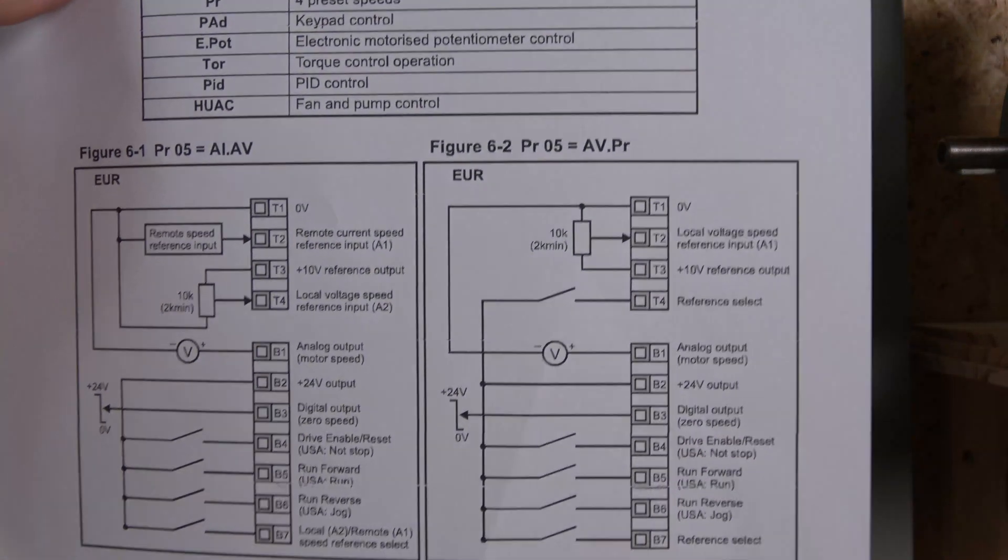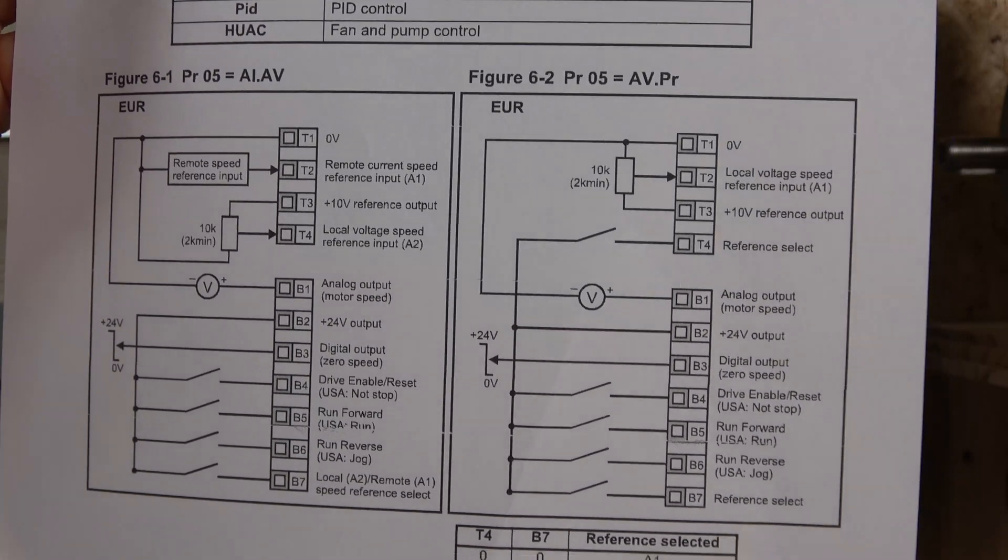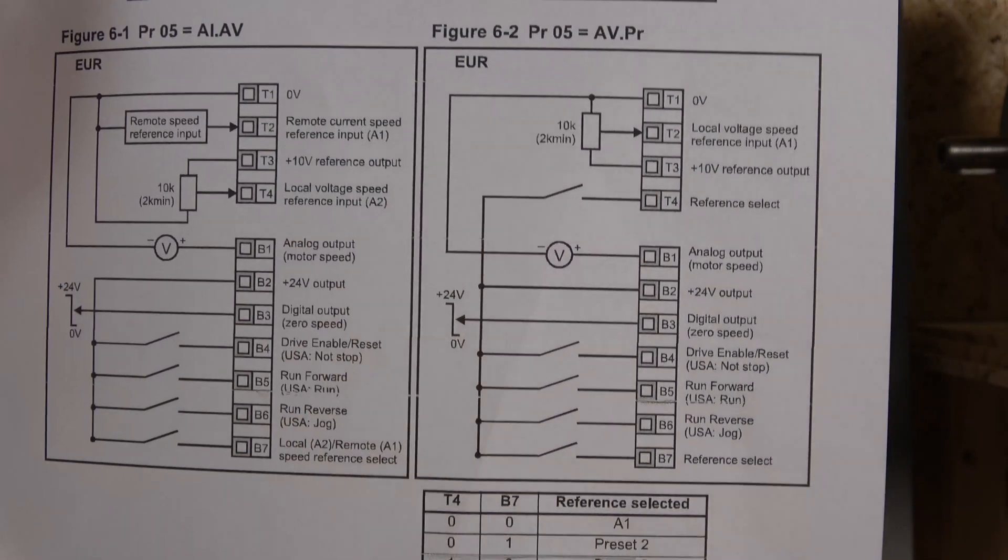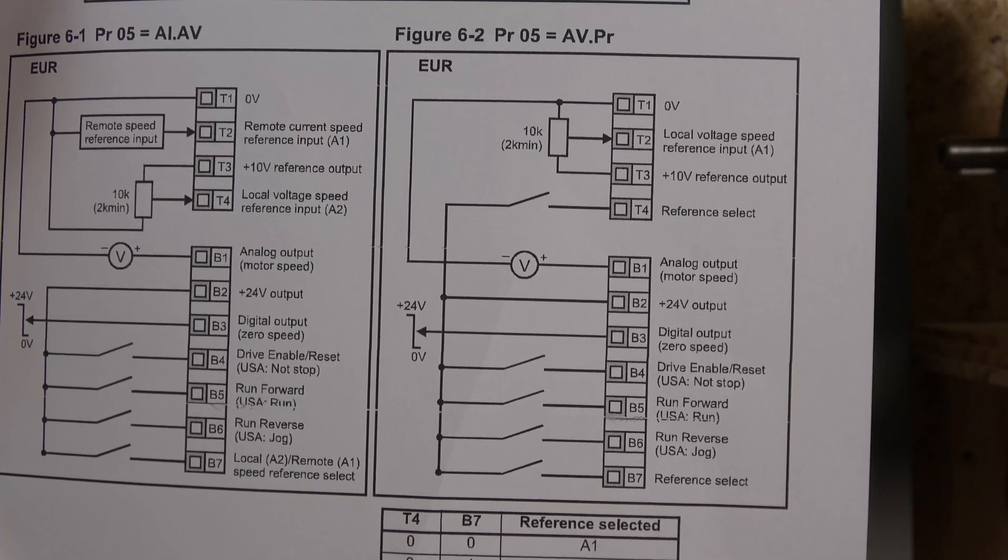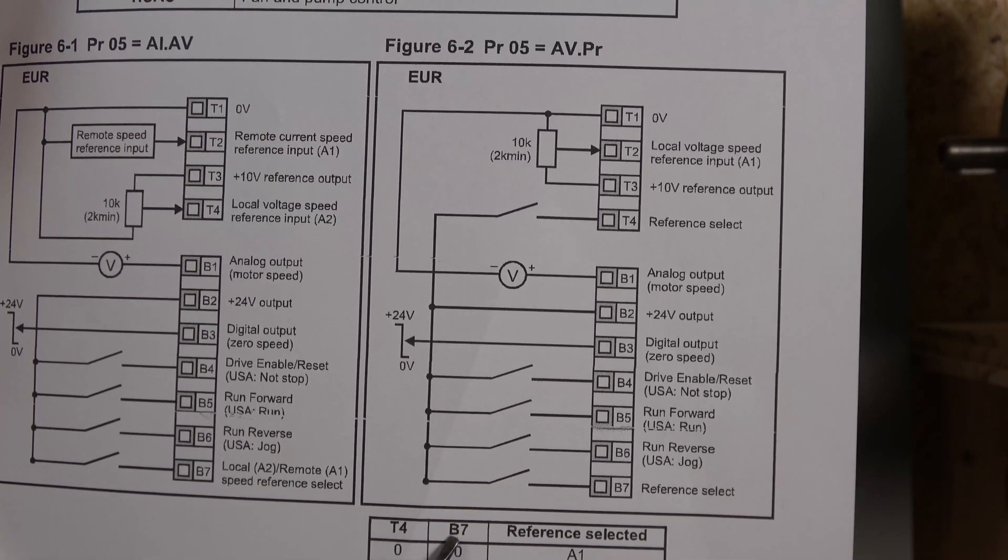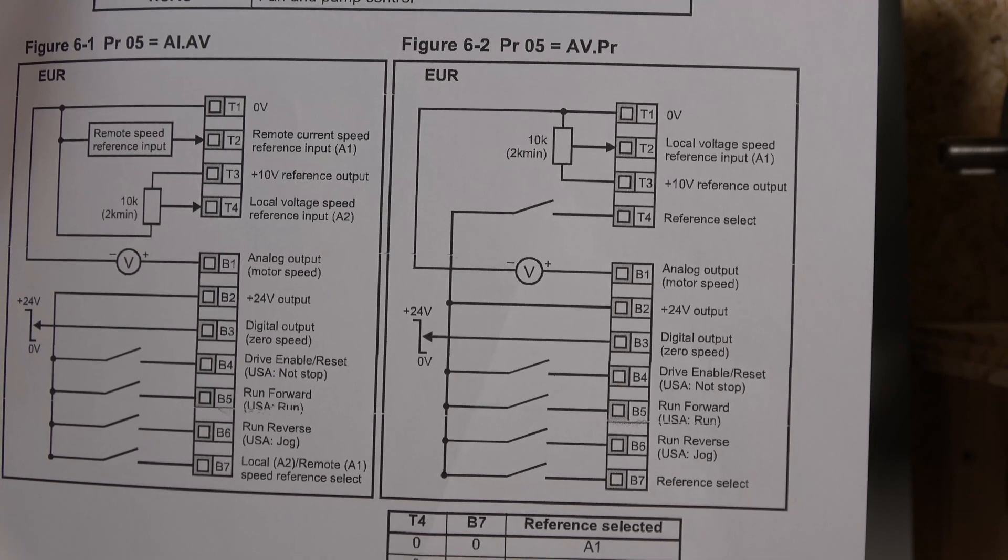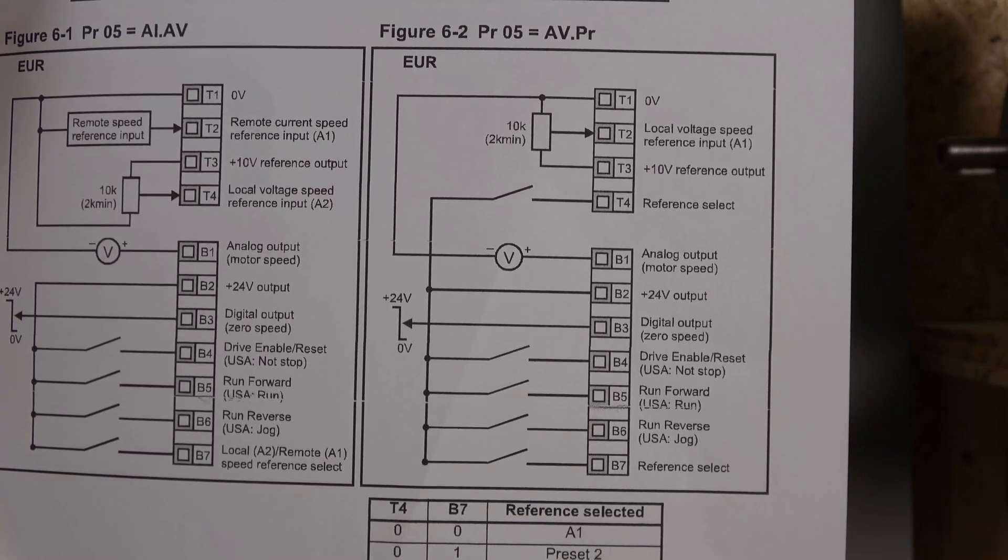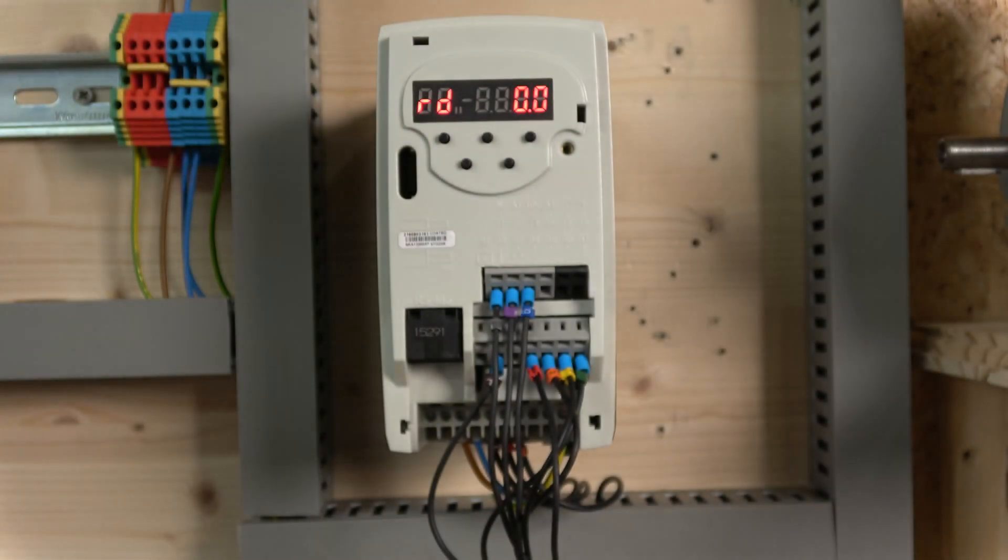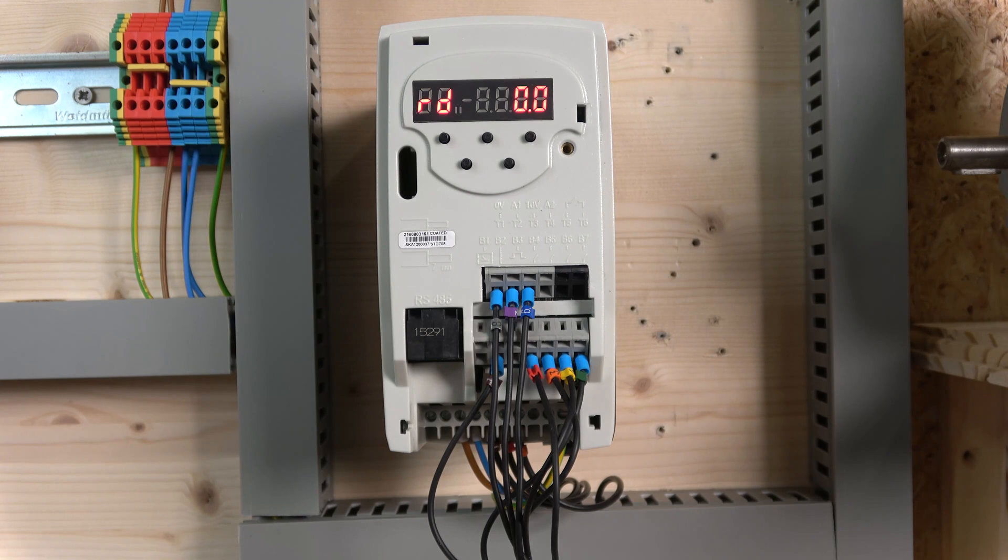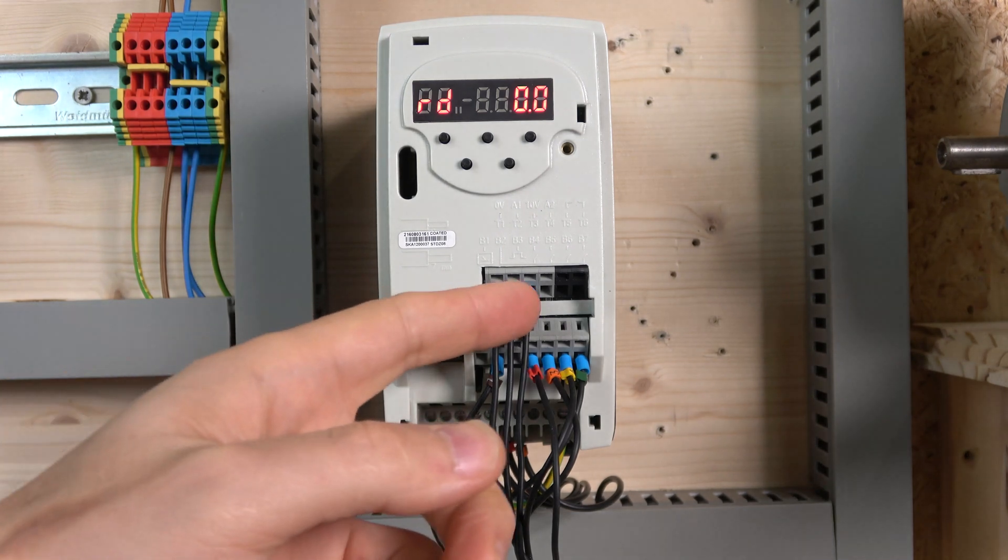There's an easy way to do this. If you follow this parameter here, which you can do in Parameter 5, if you change that one to AVPR, you will receive different selections. Once you close this guy here, as you can see, if you close B7 and keep T4 open, you will have Preset 2. And that Preset 2, you can just enter your frequency, whatever jog frequency you'd like, and it will pretty much work as a jog frequency without complicating things far too much.